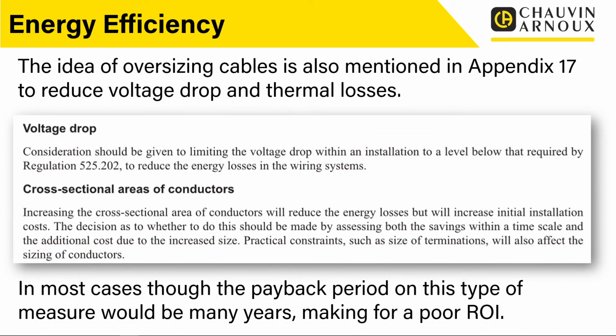Now, a bit of a wacky idea, this one, but it is technically correct. So the idea of oversizing cables is also mentioned in Appendix 17 to reduce volts drop and thermal losses. So they're actually talking about making your cables bigger to reduce the losses within those cables. However, I have done some maths on this and I've done some examples, and in most cases though, the payback period on this type of measure would be many years, making for a poor return on investment.